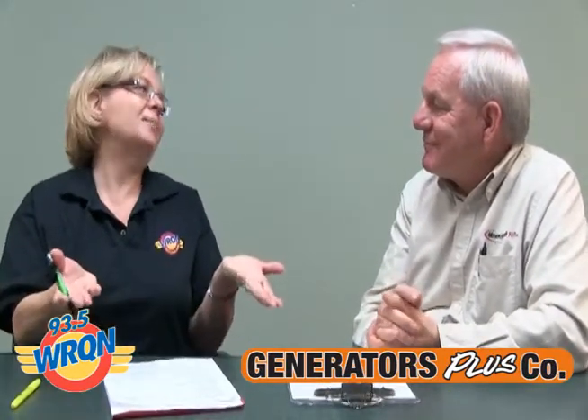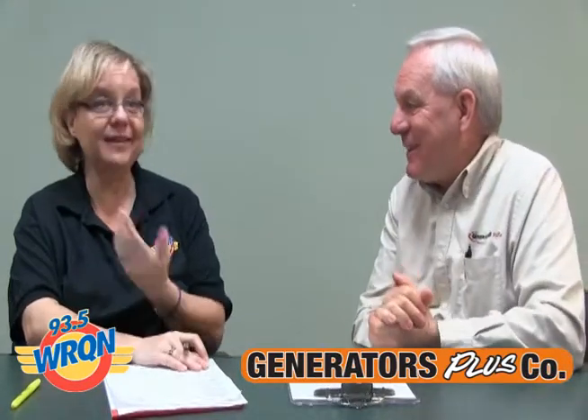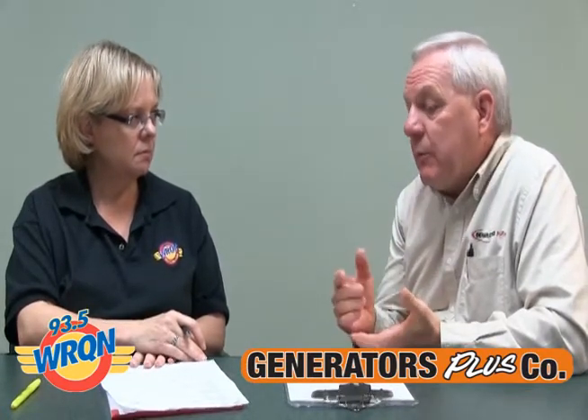All right. Let's talk about people who say, it can't be that complicated to do a portable generator, Dave. I'll just do it myself. Maybe not the best idea. No, maybe not. I think a lot of people are under the assumption that you just buy this generator, you get a big cord, and you plug it in, and that's it. Yes, that's what I would think. No, it doesn't work that way. A lot of times they don't know the codes, and they don't know the particulars on how you're supposed to do it, or what size gas lines to run to the generator. That's probably the number one fault we see when people do it themselves.